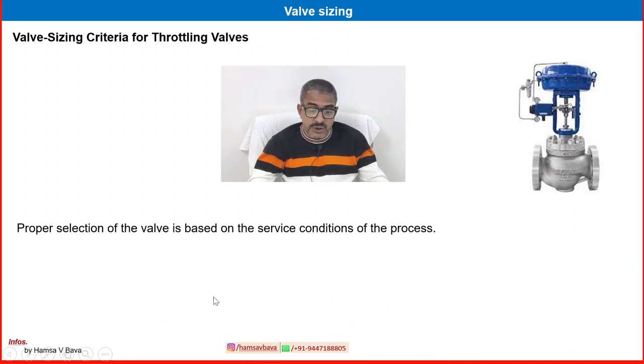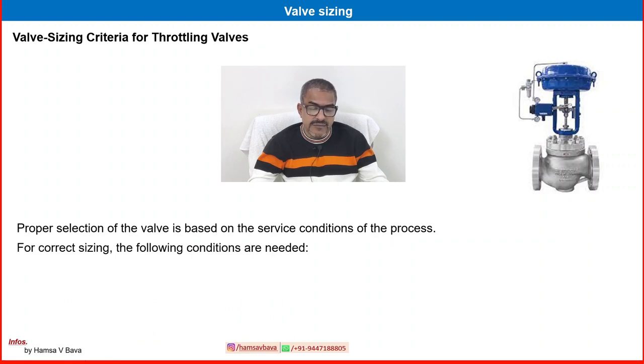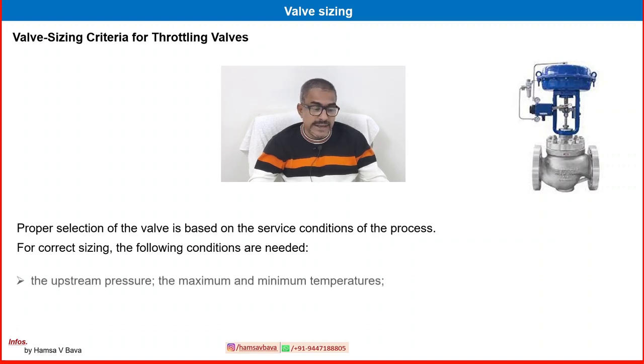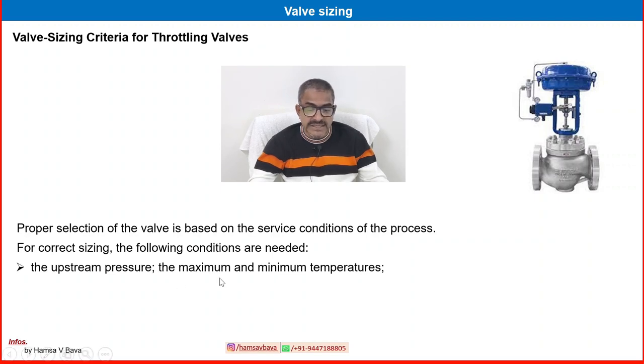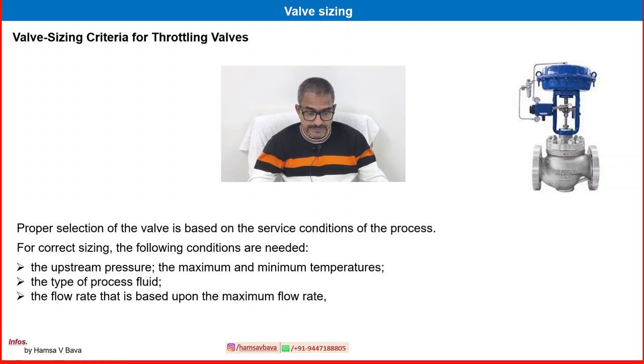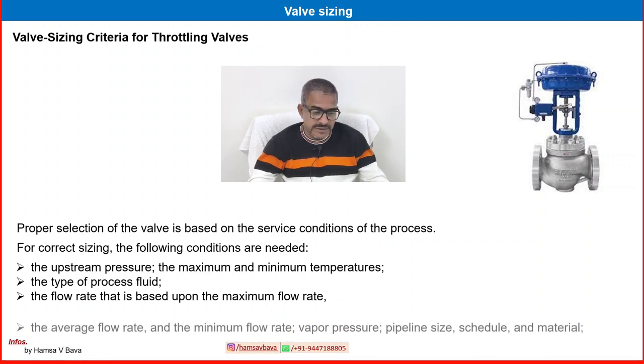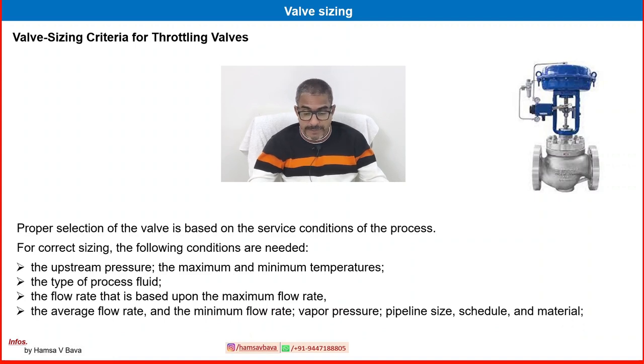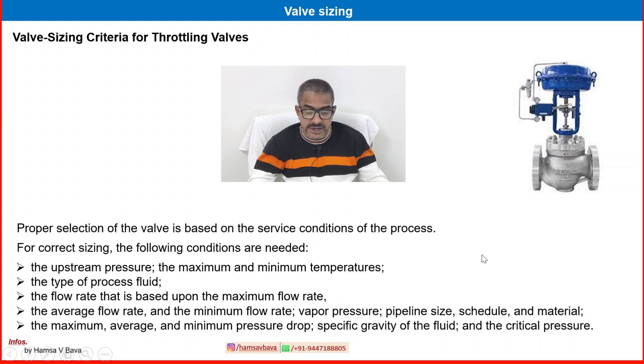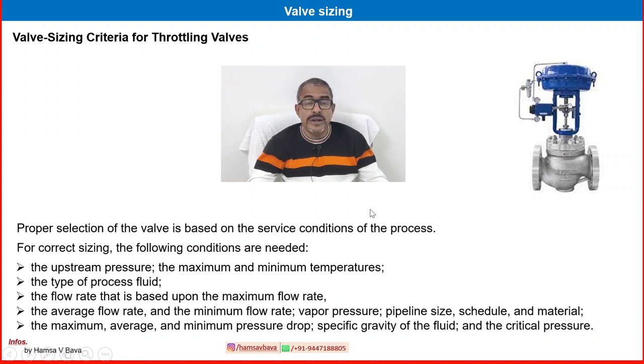Proper selection of the valve is based on the service conditions of the process. For correct sizing of throttling valves, the following conditions are needed: upstream pressure and maximum and minimum temperature, type of process fluid, flow rate (maximum, average, and minimum), vapor pressure, pipeline size, schedule and material, maximum/average/minimum pressure drop, specific gravity of the fluid, and critical pressure. These are the important factors affecting valve sizing for throttling valves.